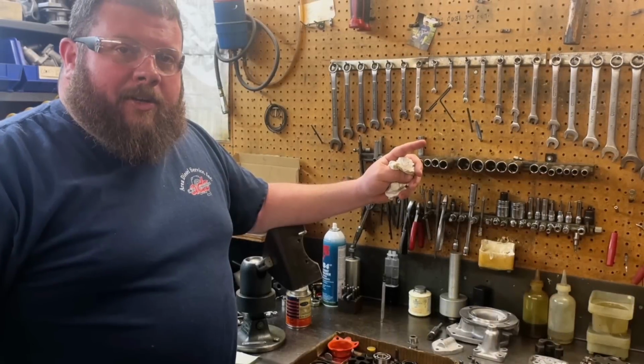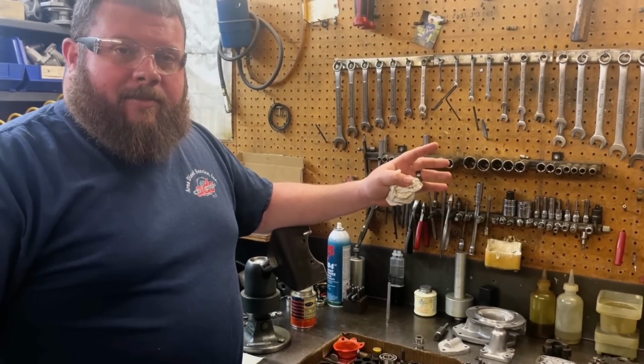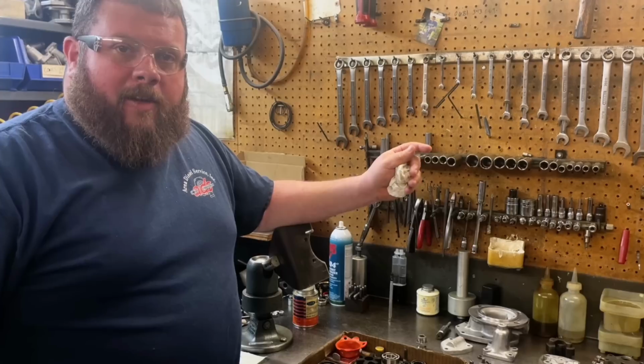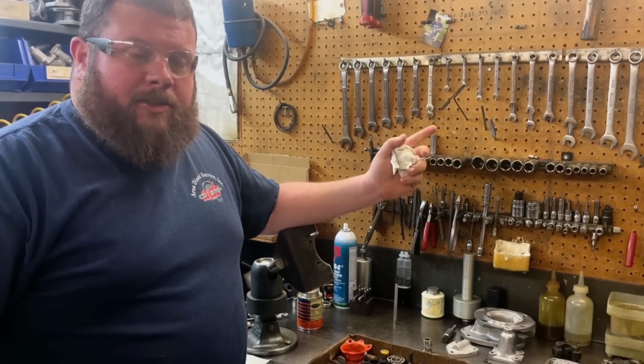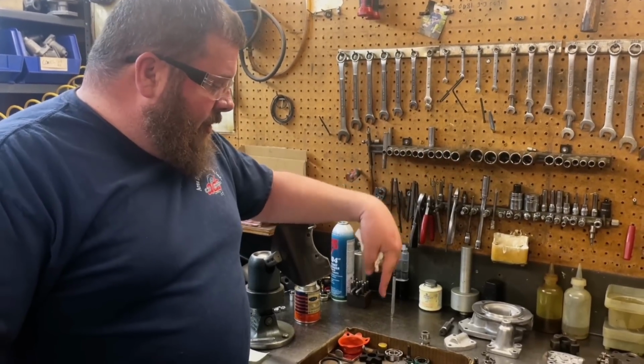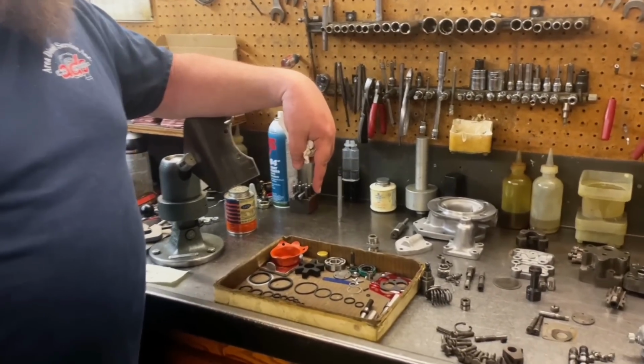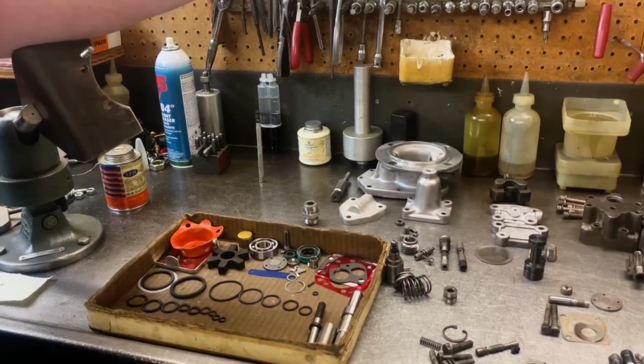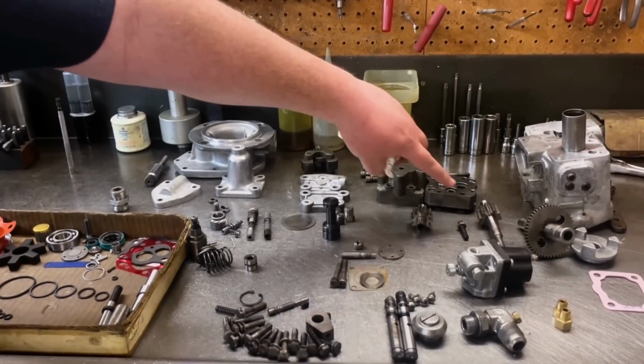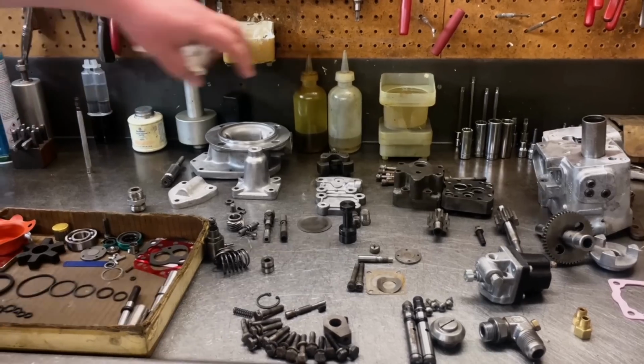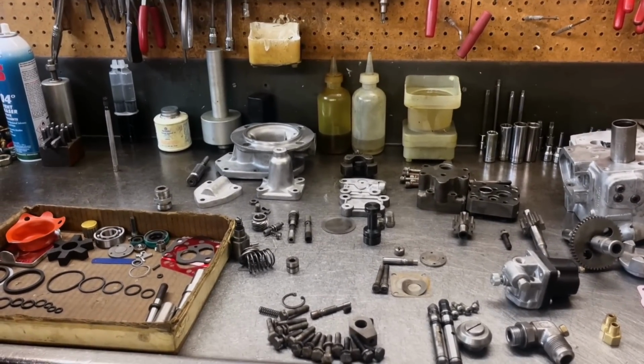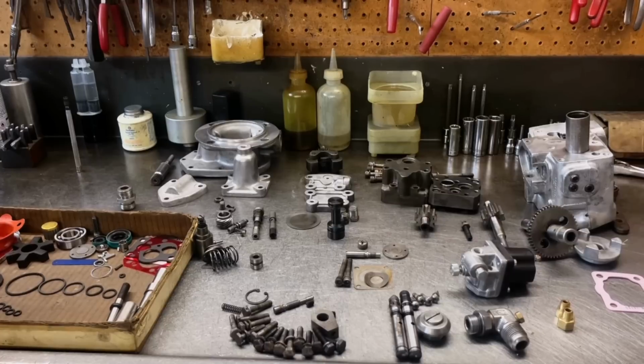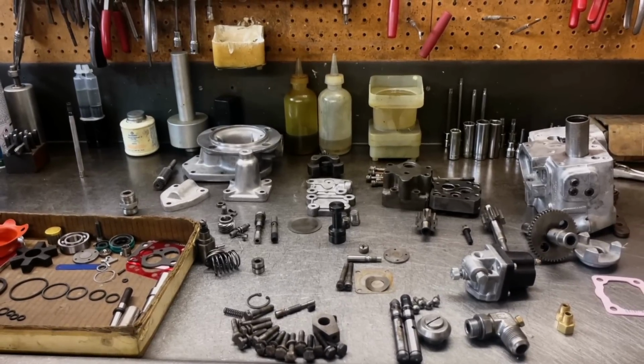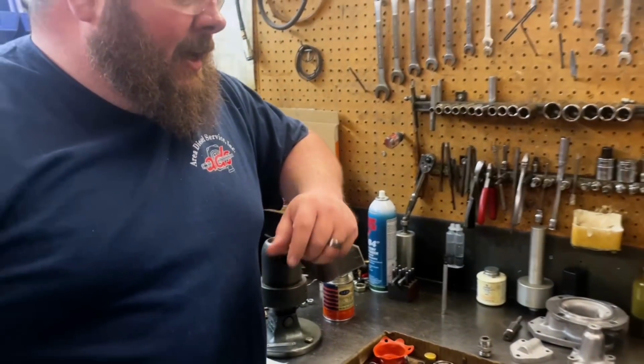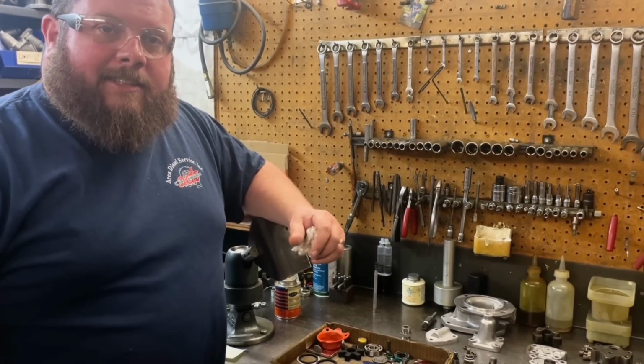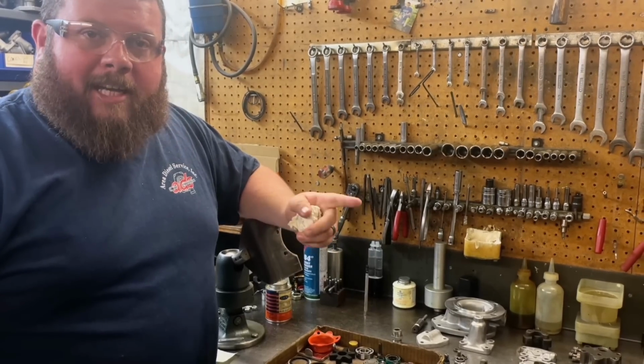We're back in the build-up room. We've cleaned everything again after honing and done a more thorough inspection of all the components, particularly those we're going to reuse, to make sure everything's good. We've got our new components staged in the box here, and everything we're going to reassemble scattered on the bench. We'll probably start on the gear pump end, the pulsation damper, and bring you through some of the reassembly. We probably won't capture the whole thing, but we'll show some of it going back together and try to hit on some of the functionality. Then once it's built, we'll show testing and calibration of this pump, and meet you back at the parts counter.